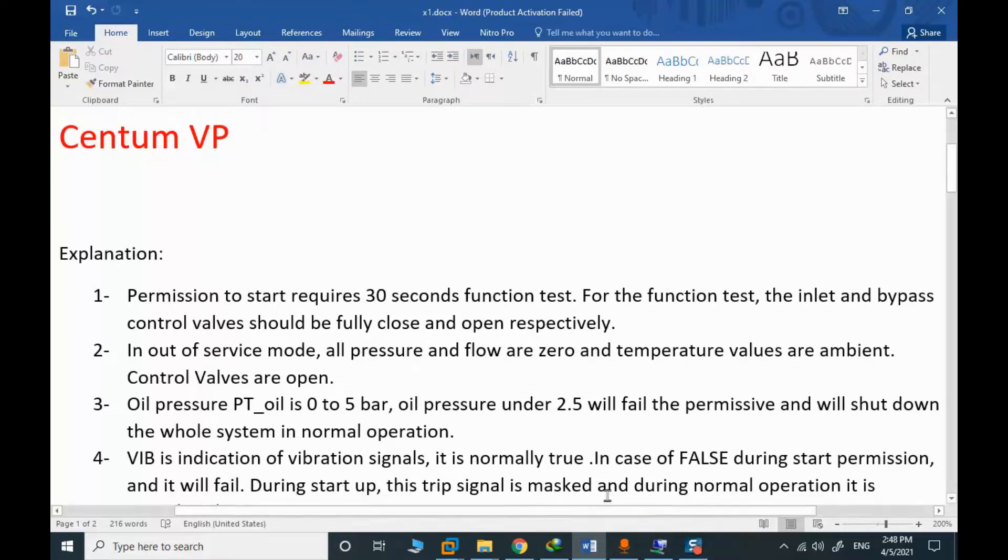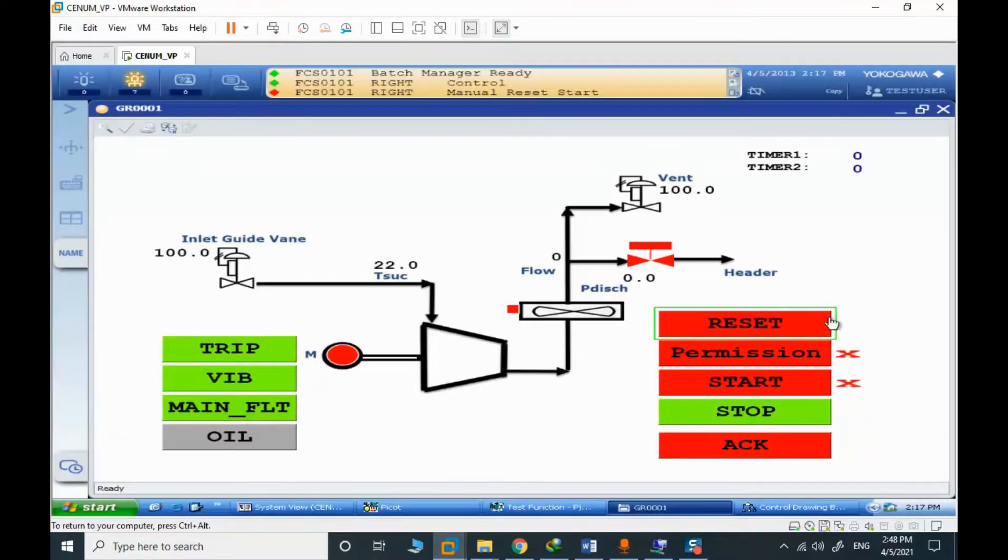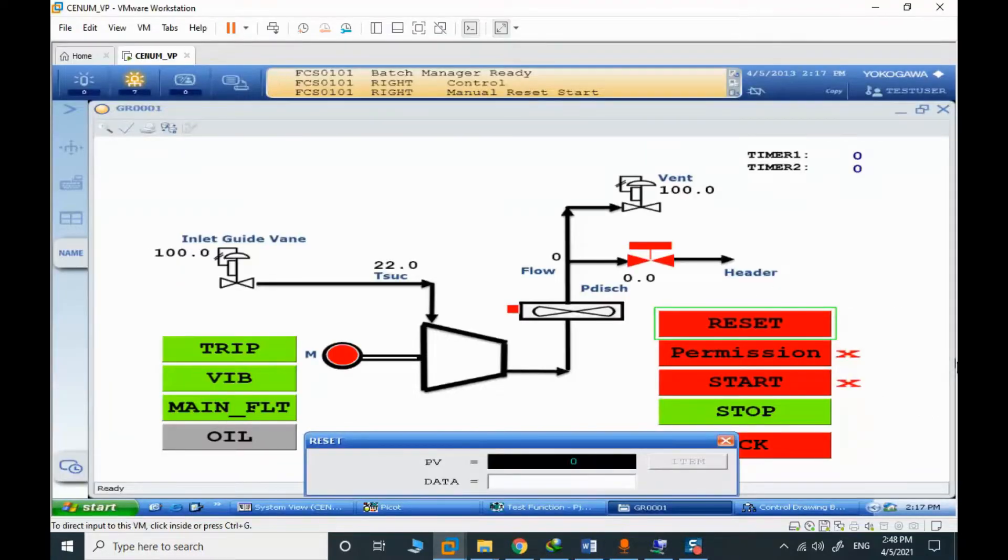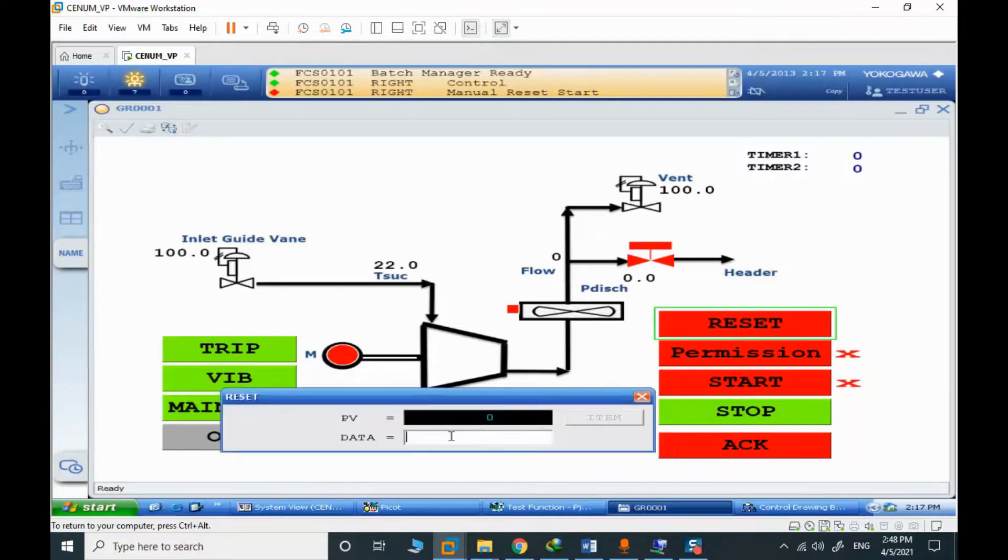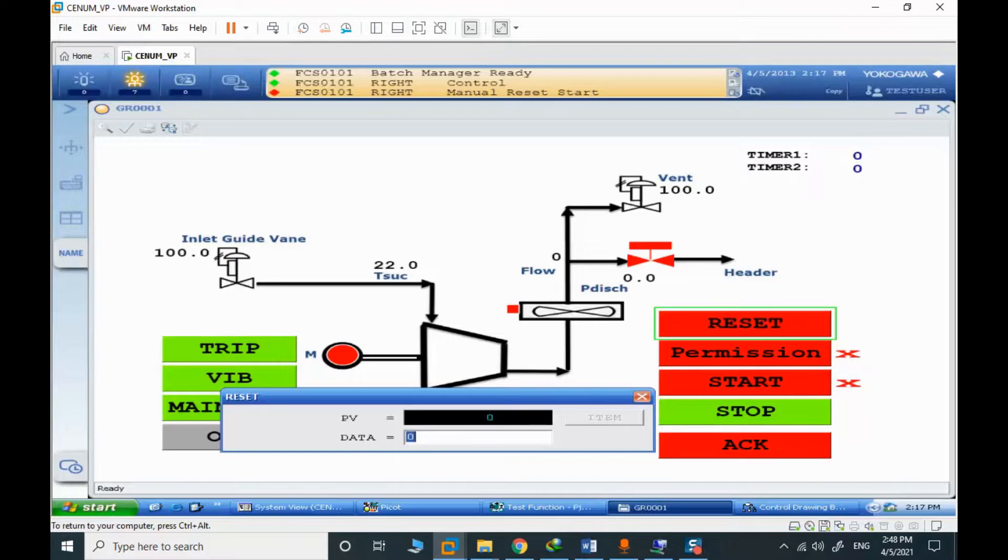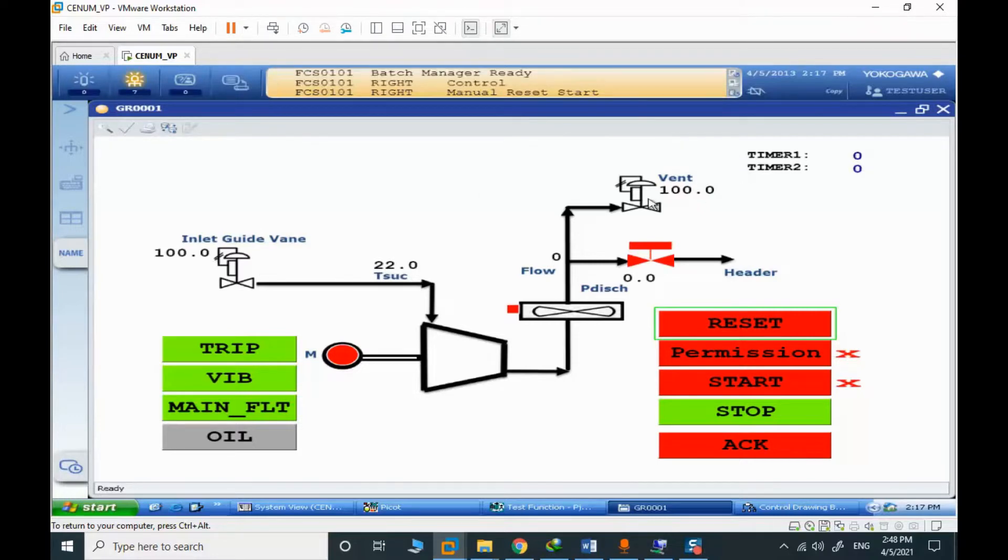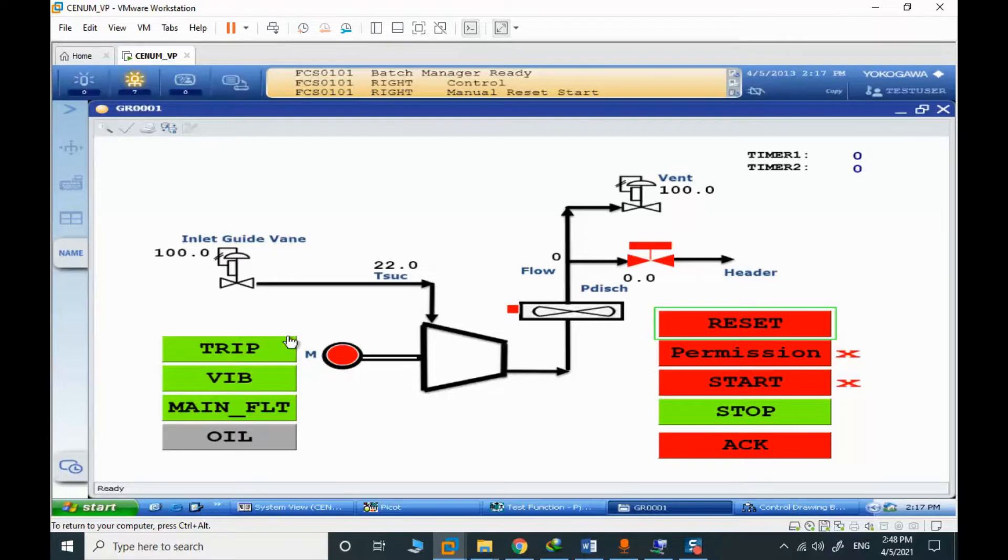The first working state is the reset or out of service. When we are in the out of service mode, the temperature values are ambient temperatures and pressure and flow are zero. Valves are all open and we consider that vibration, main fault, and other trip signals are normal. They are normally true.